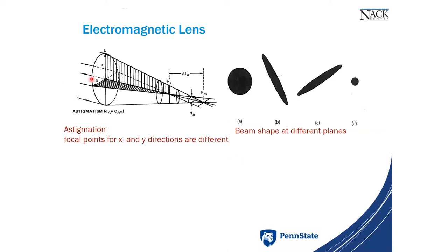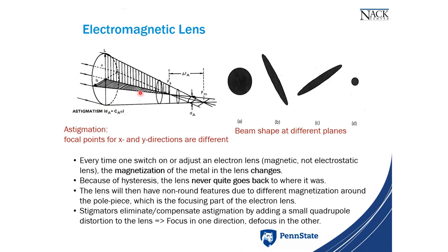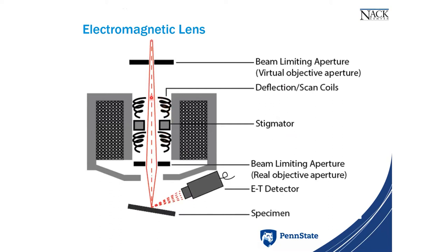Another problem: the magnets are not perfectly symmetric, so we can't focus equally in X and Y simultaneously. Instead of circular beam spots, we get ellipses — X is focused but Y is not. To counteract this, we use a stigmator, which applies corrective fields. I'll demonstrate using the stigmator when I operate the SEM to get a nice circular beam focusing in both X and Y.